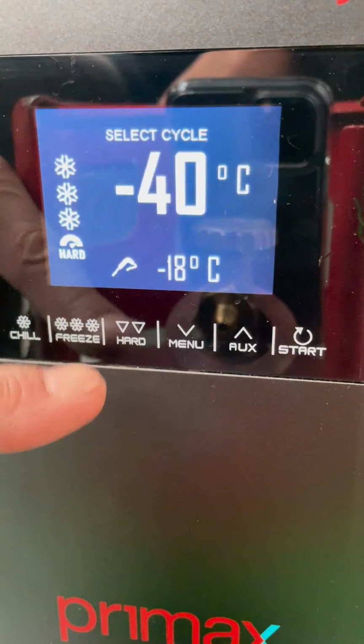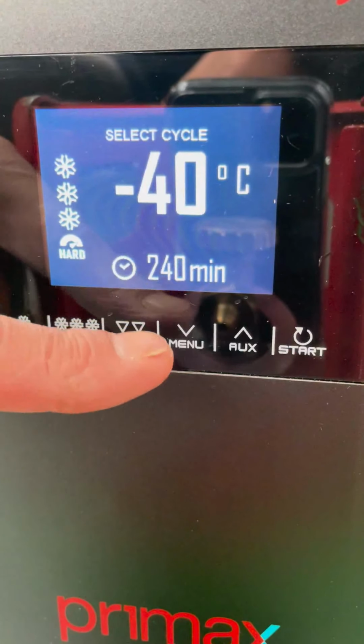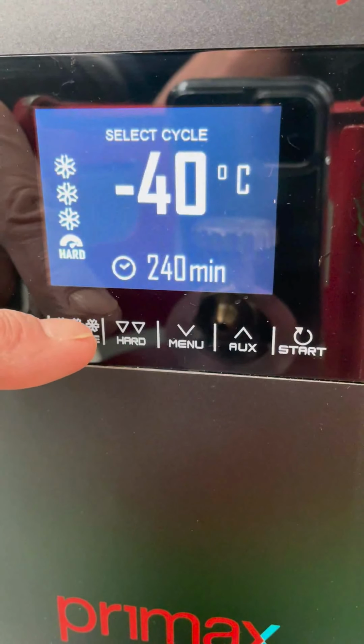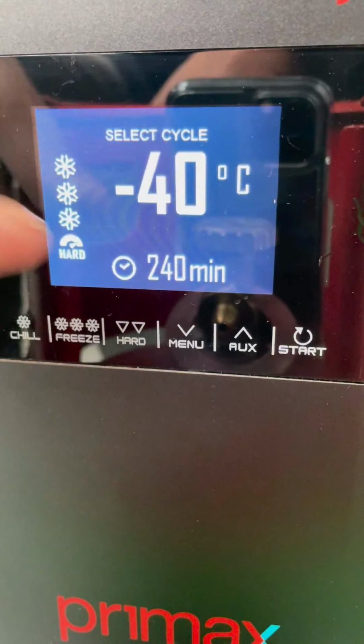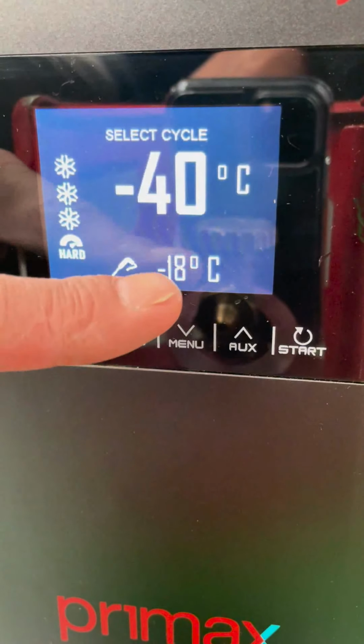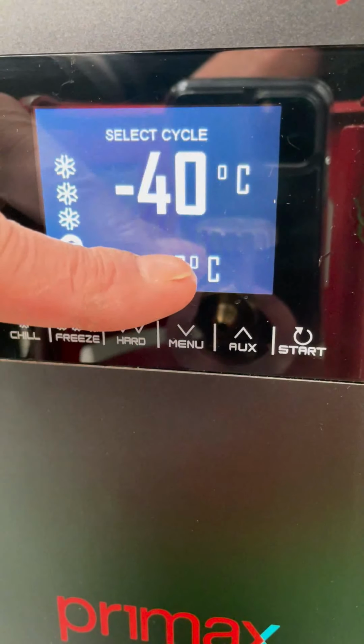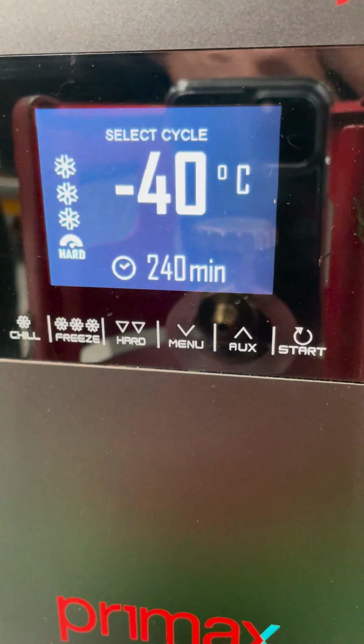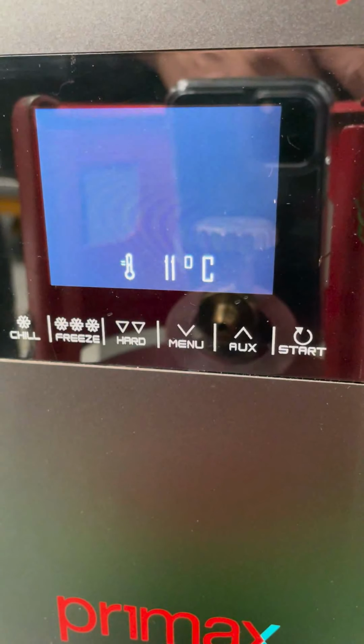You have also the shock freezing. Shock freezing using the core thermometer and using time, adjustable again, you decide. And hard and soft. Hard is the classic shock freezing cycle, where you use all the power of the compressor to reach minus 18 in the core if you use the core thermometer, or lowest possible air temperature for 240 minutes. So minus 18 in the core, the goal, or 240 minutes. Also, at the end of these two cycles, one by thermometer, one by time, the machine will switch automatically to conservation mode, meaning that the shock freezer will work like a freezer, keeping the minus 18, minus 20 temperature of the product inside the shock freezer.